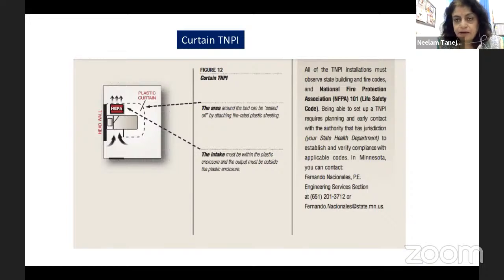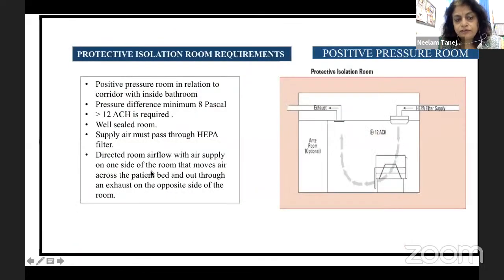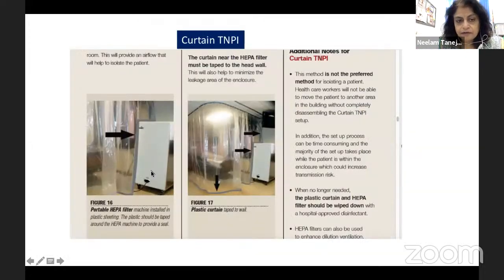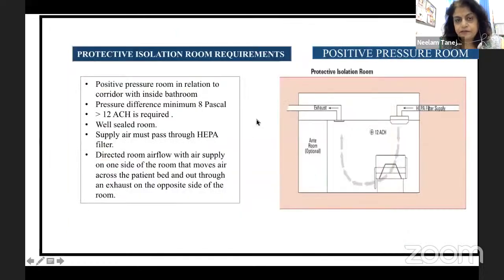Then you could have curtain isolation, a temporary negative pressure isolation. These were extensively used by the West. In this, you have a plastic curtain. The area around the bed can be sealed off by attaching this fire-rated plastic, because there is a very high risk of fire. So this should be fire-rated plastic sheeting. The intake must be within this curtain, and the air is exhausted through the HEPA filter machine. This is the example. Now you have to seal around the HEPA filter machine. You have to seal to the ceiling, so there is no leakage.